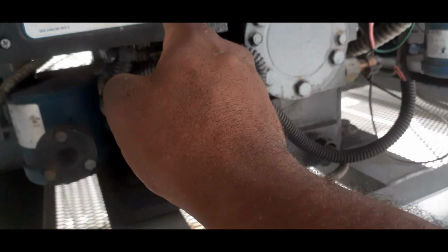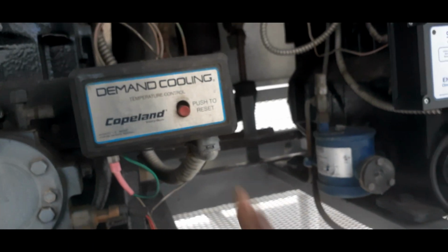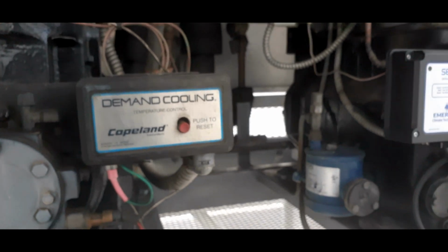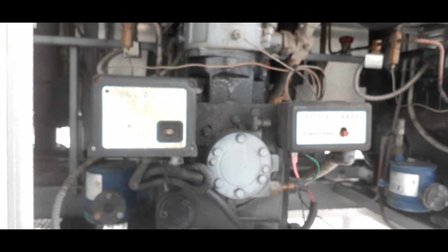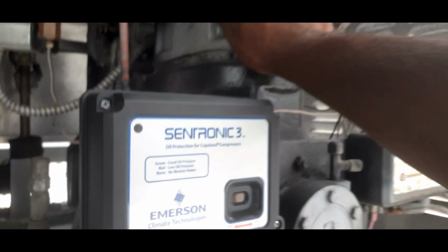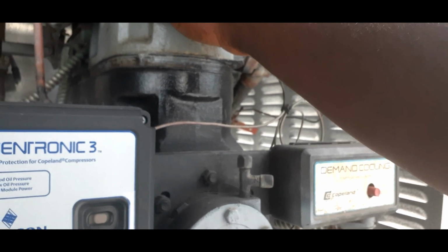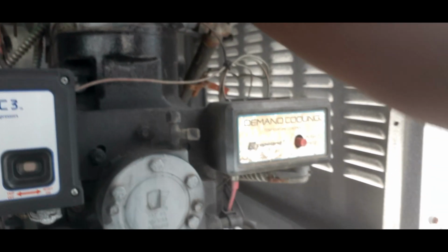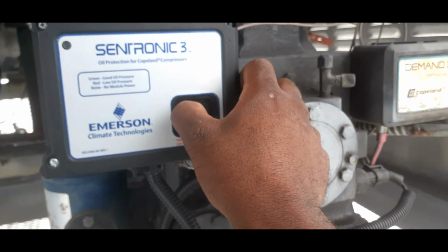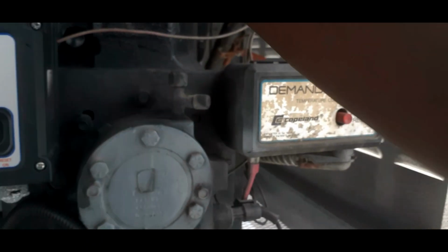Let's see if this. That's not tripped. That one's off on demand cooling. And well, we don't have no amps here. Head fan is running. This feels warm, but I didn't have no amp draw on it. That tells me that we probably tripped on demand cooling also. Nope, not on oil. Something's up with this, baby. Whoa, that suction bell is hot. Probably off on overload.